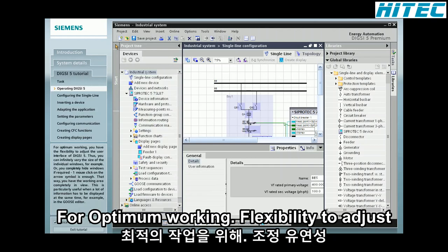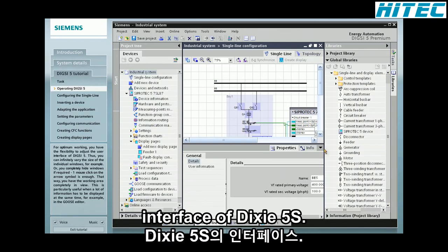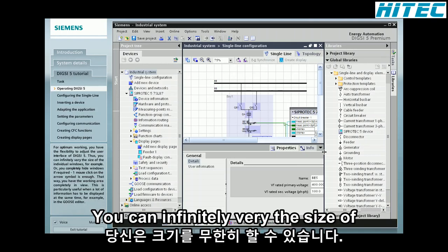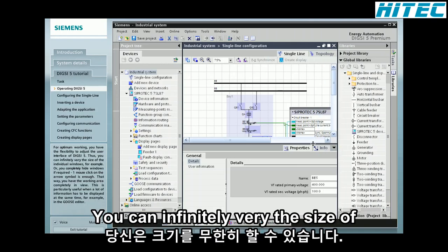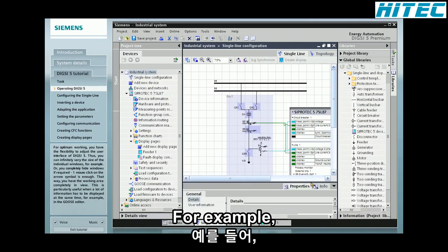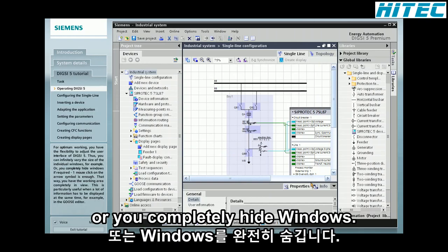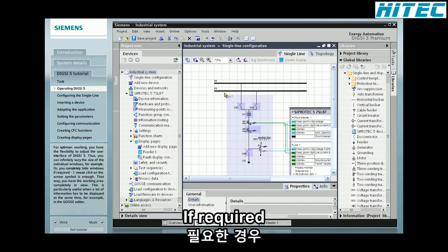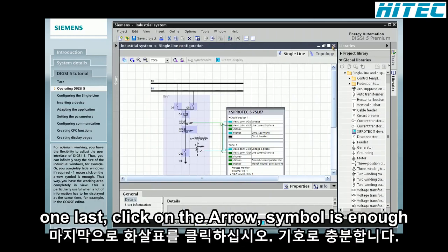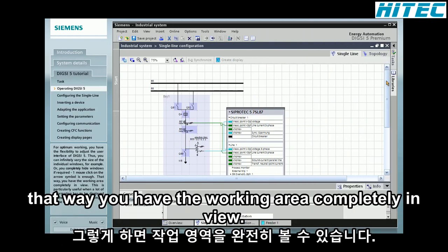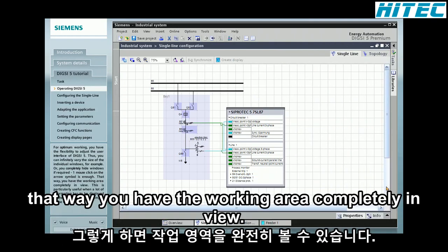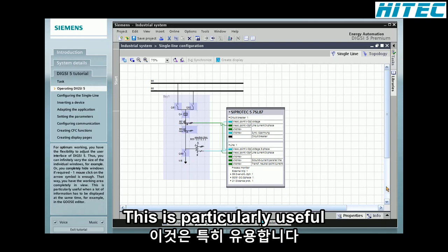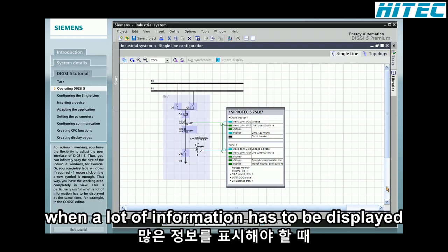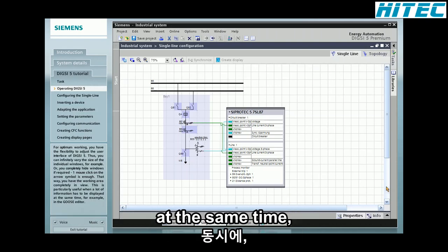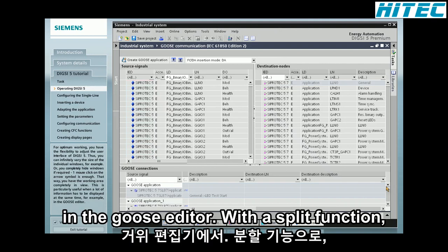For optimum working, you have the flexibility to adjust the user interface of DIGSI-5. Thus, you can infinitely vary the size of the individual windows, for example. Or you completely hide windows if required. One mouse click on the arrow symbol is enough. That way, you have the working area completely in view. This is particularly useful when a lot of information has to be displayed at the same time, for example, in the GOOSE editor.